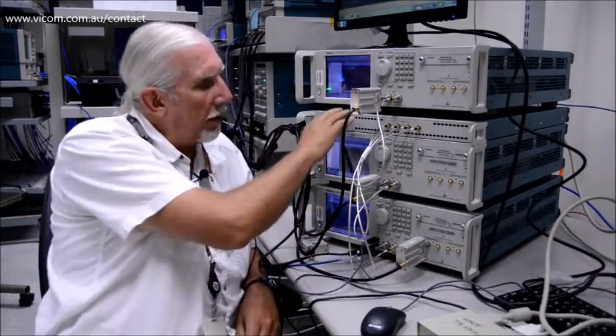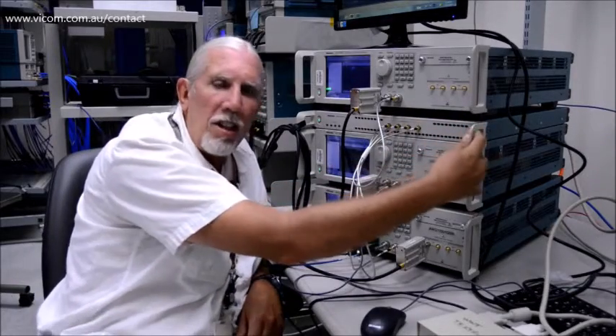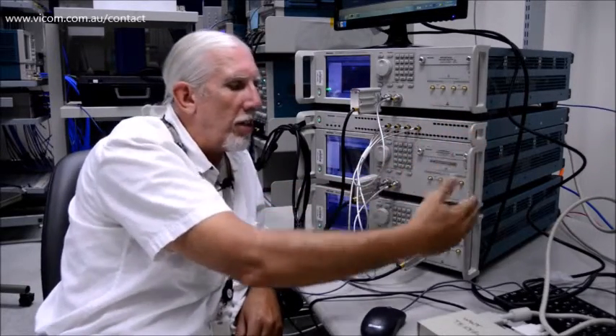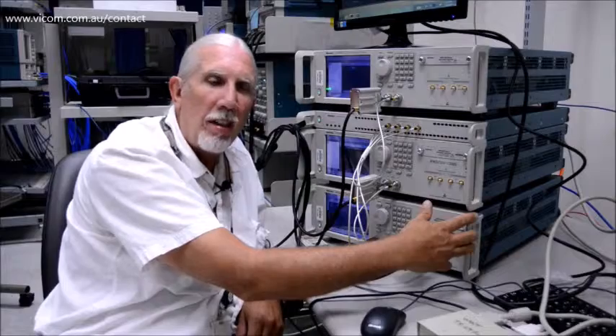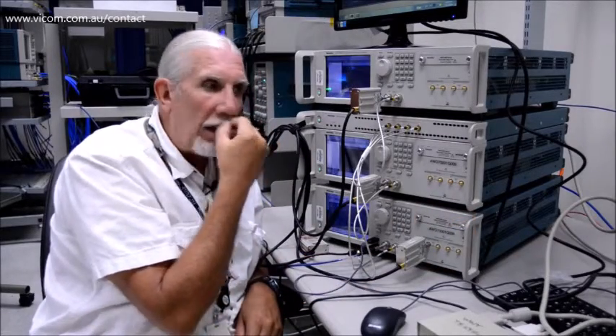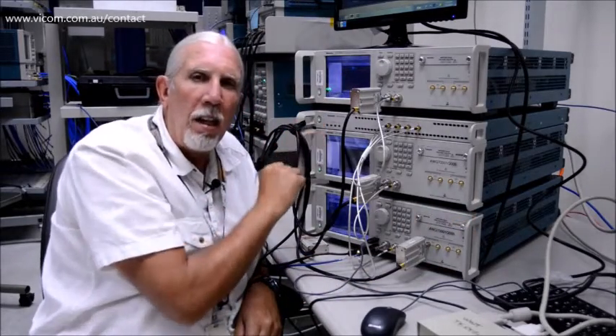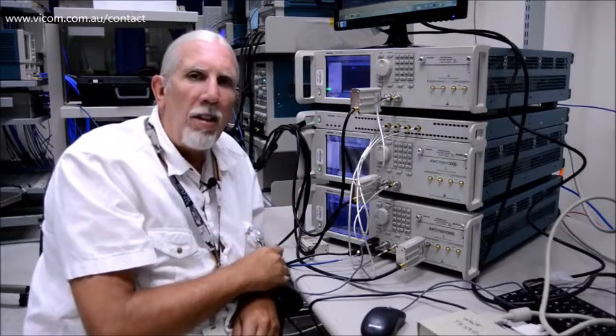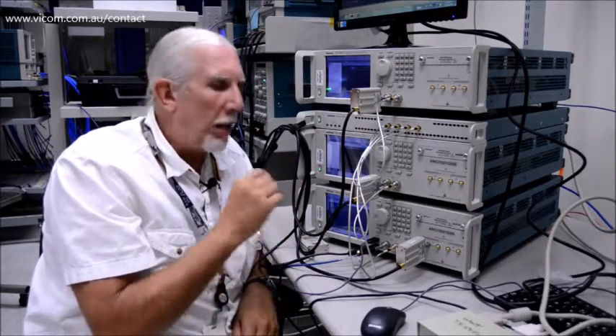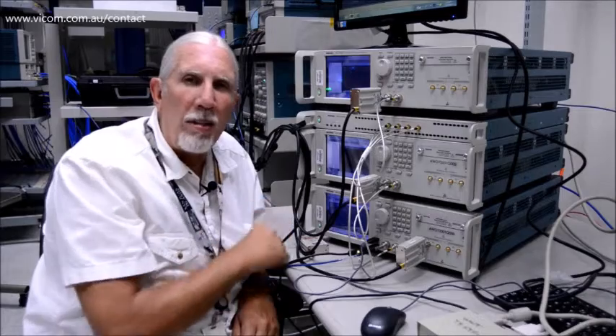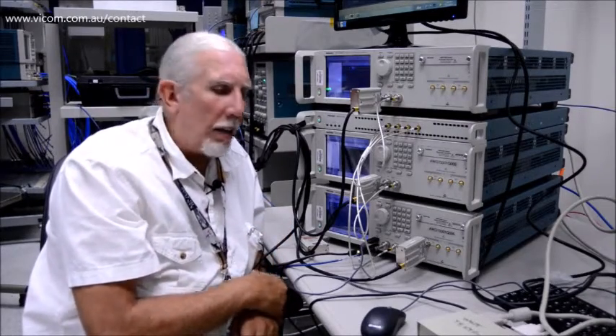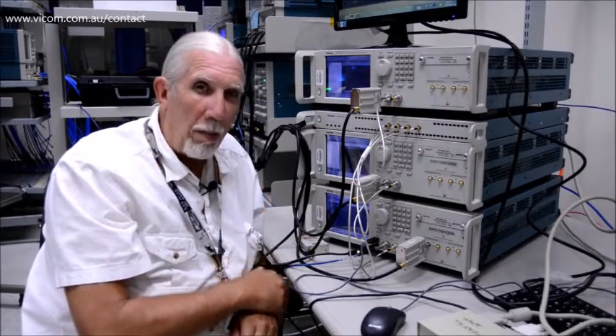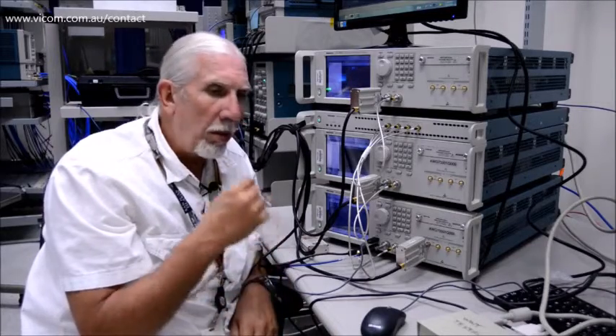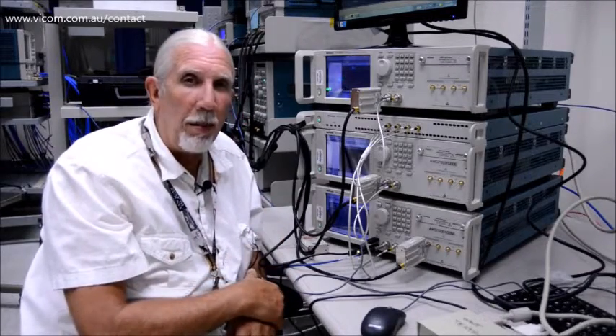This particular synchronization hub will allow the synchronization of up to 4 AWGs simultaneously. This gives you the capability of synchronizing all of the outputs of each individual AWG such that they all coincide with the clocks and the trigger requirements for the application. So all of the AWGs will fire at the same time.